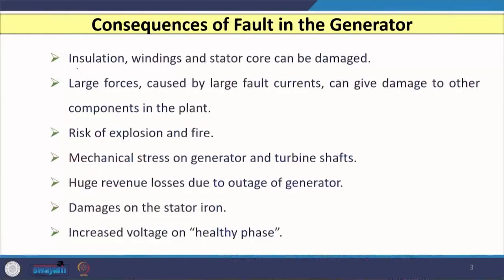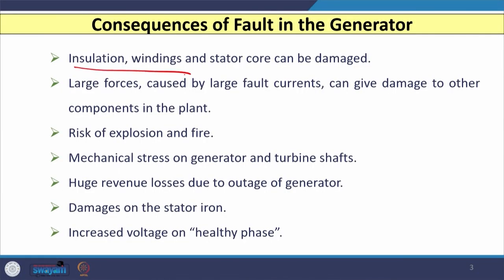If reverse power is not detected, damage can occur to the turbine — whether it is a steam turbine, hydro turbine, or diesel or gas turbine. If any fault occurs in the synchronous generator, the consequences include damage or deterioration of insulation, windings can be damaged, or the core of the stator can be damaged. This is one of the consequences of a fault inside the generator if it is not cleared.